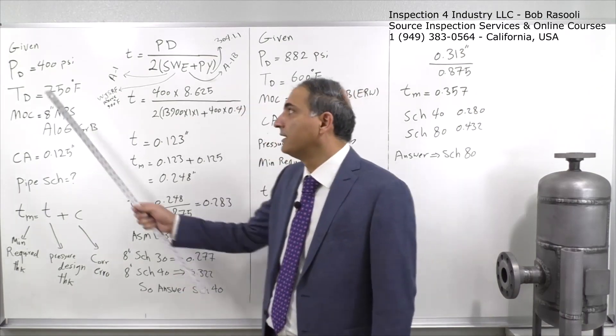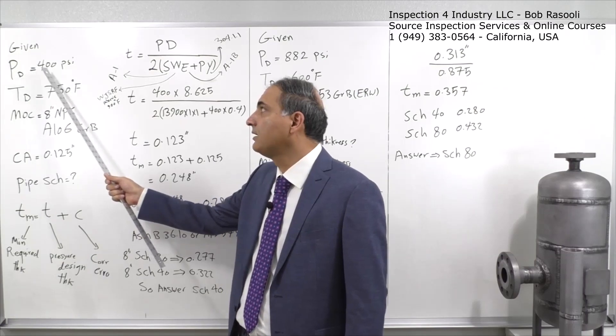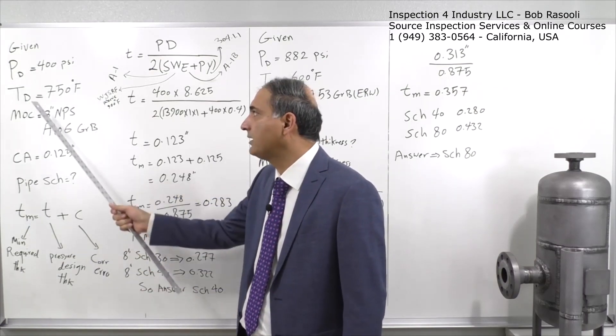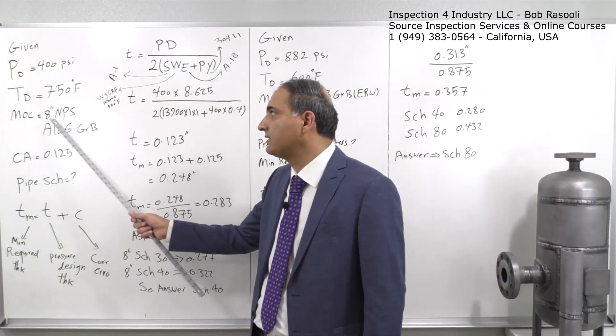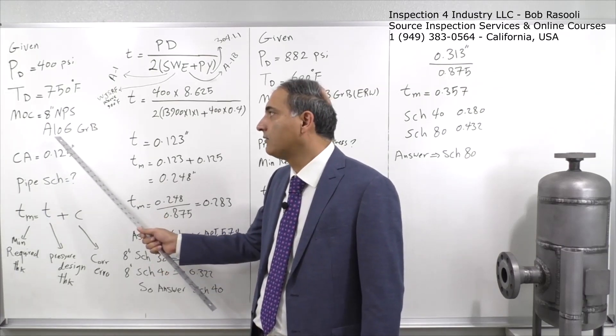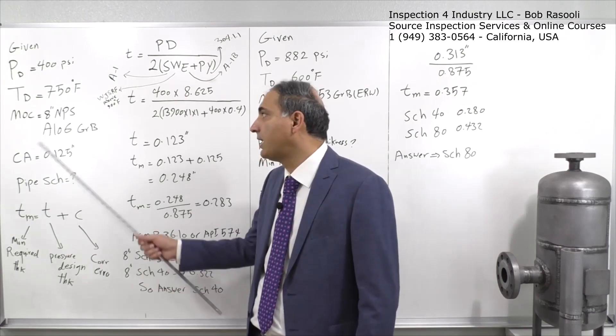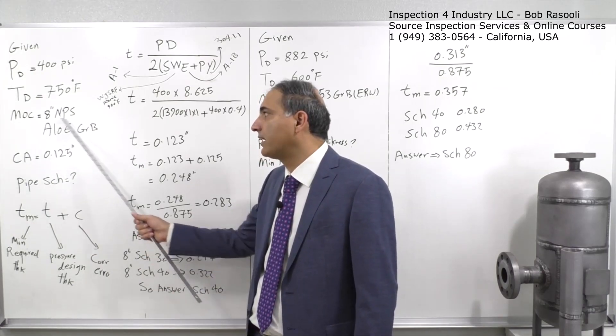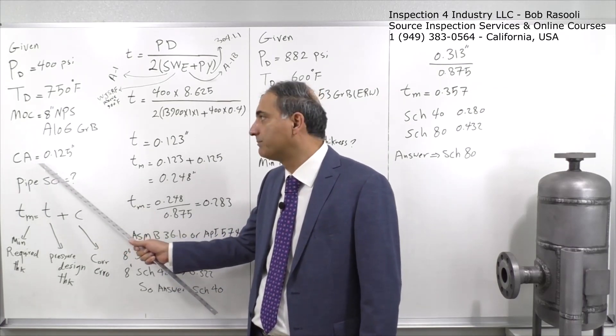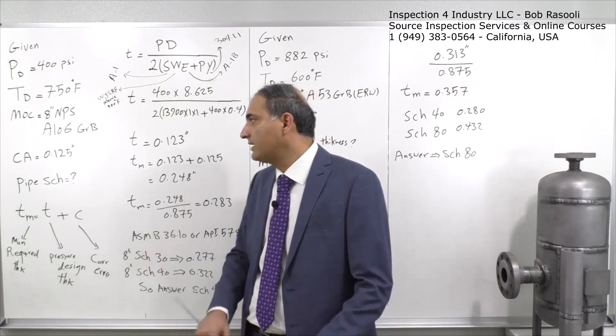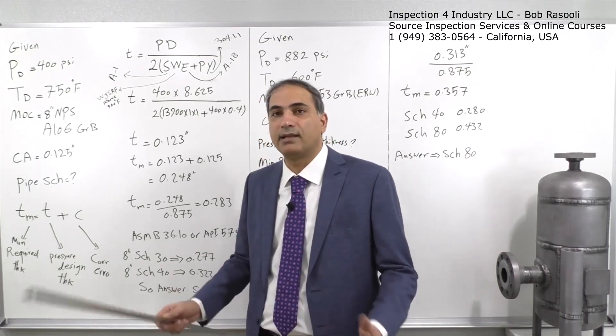Our first problem involves a pipe where the problem provides us with a design pressure of 400 psi. Our design temperature is 750 degrees Fahrenheit, and our material of construction is 8-inch NPS (nominal pipe size) A106 Grade B — a very common seamless process piping material. The problem also provides a corrosion allowance of 0.125 inches and asks us to determine the pipe schedule. No mechanical allowances are given.